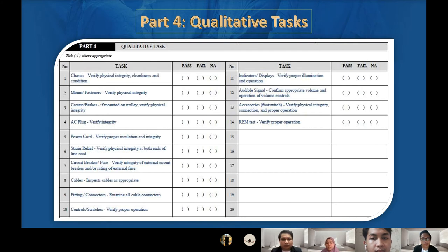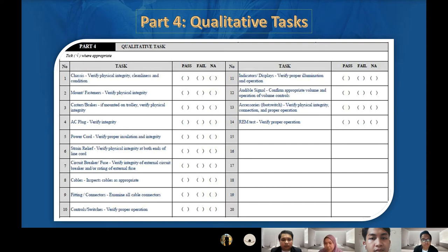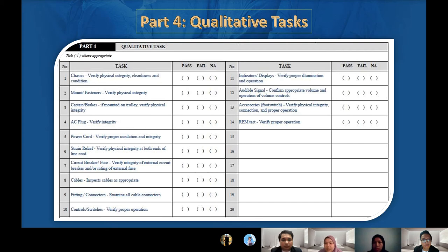For the accessory — usually the foot switch — press it to check whether it is working. If the ESU did not come together with the foot switch, mark it as not available. For the REM test pressure electrode, check the indicator: if it is green, that means you applied it properly. If it shows red, that means there is something wrong while you are applying the special electrode.